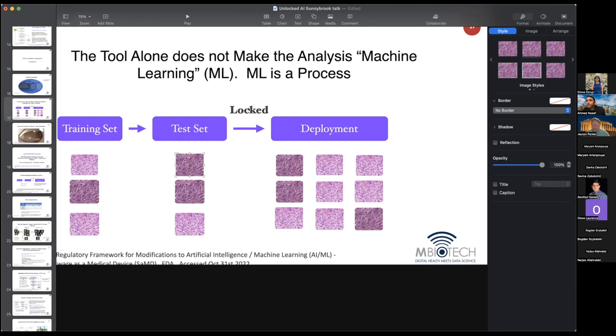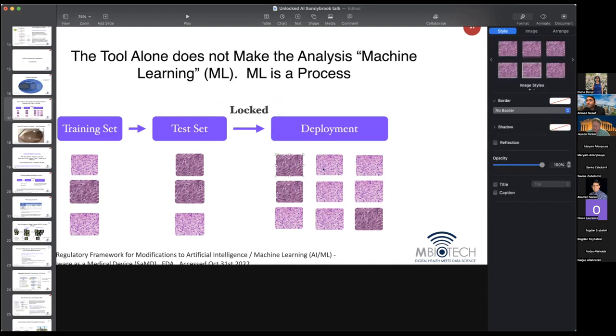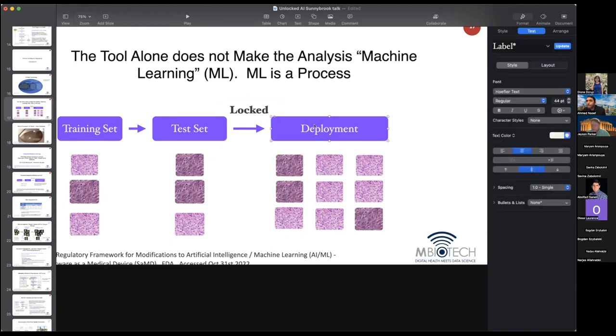Once we submit to the FDA, this neural network is going to be locked — it's not allowed to undergo any further training. It's deployed on the market and does its best job performing the classification functions it was designed for, but once deployed it does not learn. This is our current paradigm for medical device regulation with artificial intelligence.